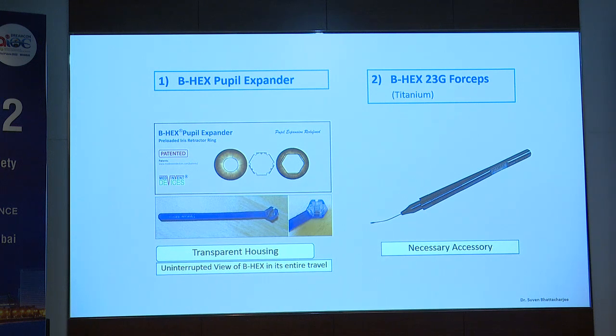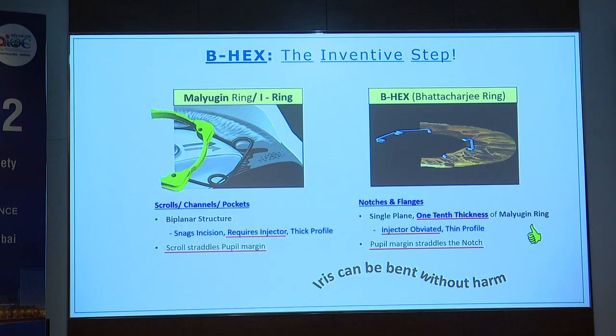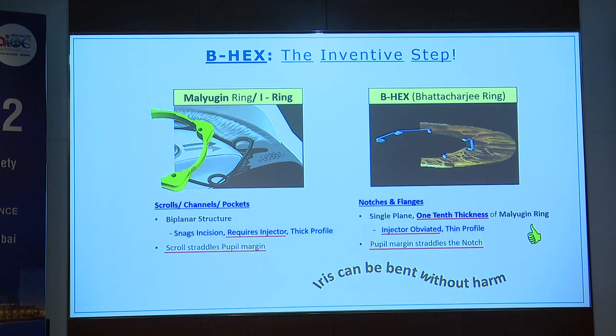The B-hex is a very thin, flexible device with thin notches, strong flanges, and tabs for holding — a hexagonal device as thin as a human hair. It has a transparent housing with constant visibility throughout placement. With an injector, you have no idea what the ring is doing inside. The inventive step of the B-hex versus the Malyugin ring is that other devices are bi-planar — the scroll and pupil margin are on different planes making the device thick — requiring an injector. The B-hex is all in a single plane: the iris bends harmlessly at the notches and can be placed and removed with forceps through a small incision.